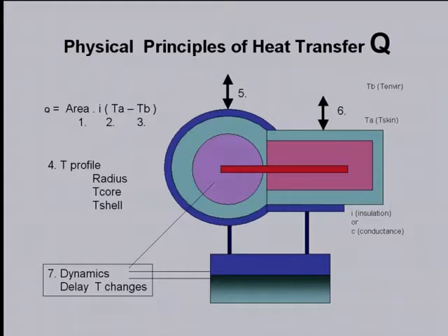You would have to consider, we have discussed it already, a temperature profile which will be different according to the radius. Lower in the shell if you cool with a cap. And then you must consider that there is a dynamics. The machine must first cool the fluid, then pump the fluid through the mattress. Then the fluid must reach the baby's surface and transmit the cold. So you have quite a dynamic. That's what I have already shown. And then, of course, there will be always some parts of the body which are exposed to the environment where you will lose additional heat. Next slide.